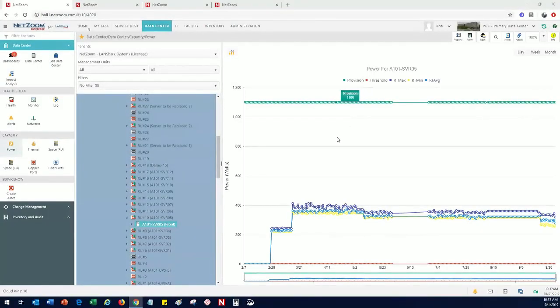All right, we're going to jump right into the NetZoom application. We talked about provisioning and rack capacity and increasing density. Here's an example of a server. This is just a default de-rating, maybe 80% of the nameplate value, roughly 1100. But looking at the real-time monitoring of this server, the maximum value we get is 413 watts. That's less than half of the provisioned value. You're literally looking at dropping this by about 50%, even if you come down to 600 just to be safe. And that's just one server. Multiply that by how many servers you have in your data center, the average 300-rack data center, and you're looking at a massive reduction in cost and power usage.